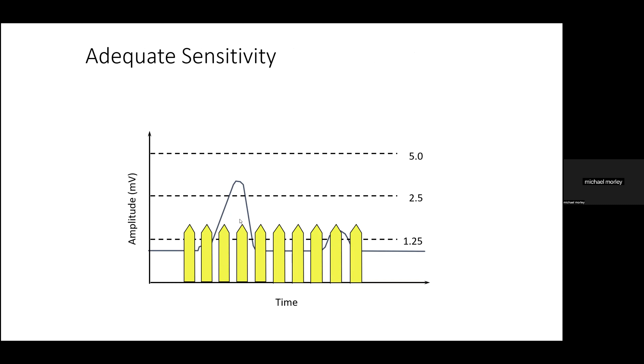So the simple rule is that if you have oversensing, so you can see here, this is from a pacemaker interrogation, you've got ventricular pacing, followed by an intrinsic ventricular beat, followed by some markers on the bottom which suggest that there's some ventricular activity. But when we look at the ECG, actually there isn't. So the device has been set up too sensitive, and it's picking up some noise or some low-level signals, which it's interpreting as a beat, and that's inhibiting pacing. So oversensing leads to underpacing.